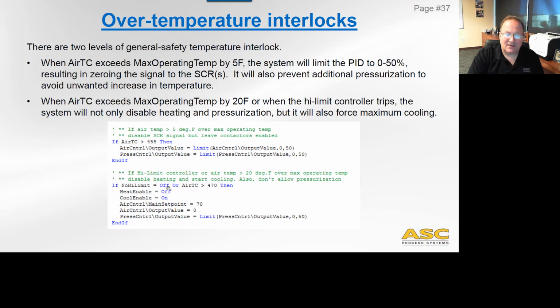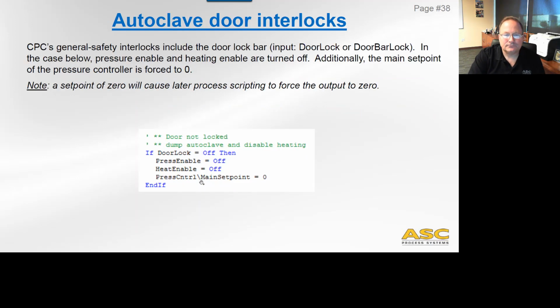And so we say if no high limit equals off or AirTC greater than 470, then I'm going to take action. Heat enable is off, which drops all the contactors. We're going to turn cooling on, set a set point to 70, and limit pressure, or basically restrict all inlet of pressure. This is going to force active cooling, maximum cooling in this case, and that is going to keep going until this specific condition is reset, okay? This is a newer feature; this one up here wasn't our standard prior to this training. It is now, okay? So there's 5 degrees above and 20 degrees above, two different conditions happening.